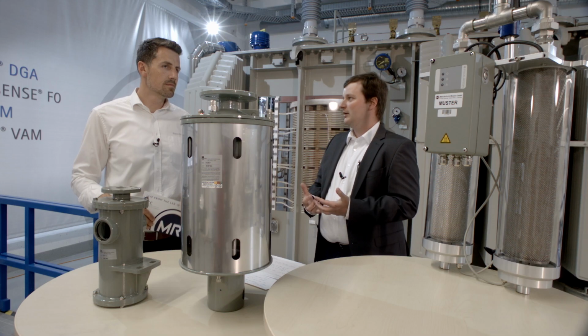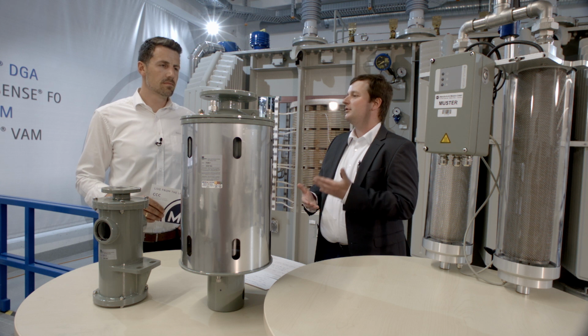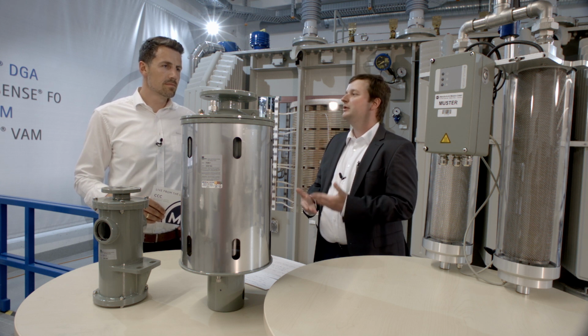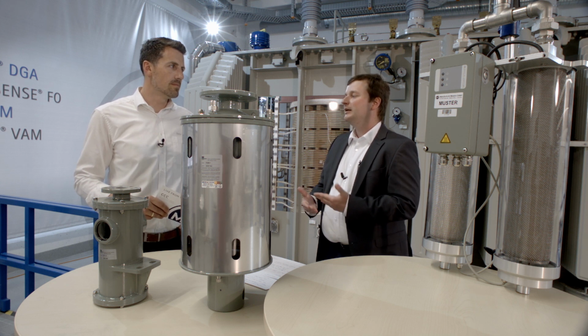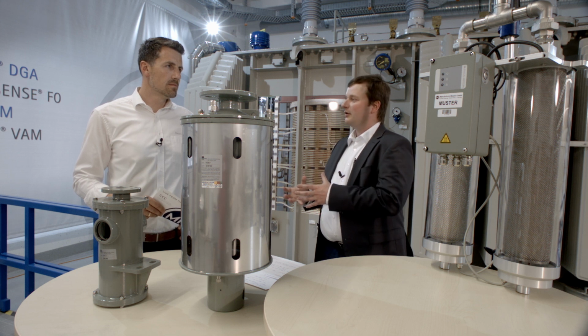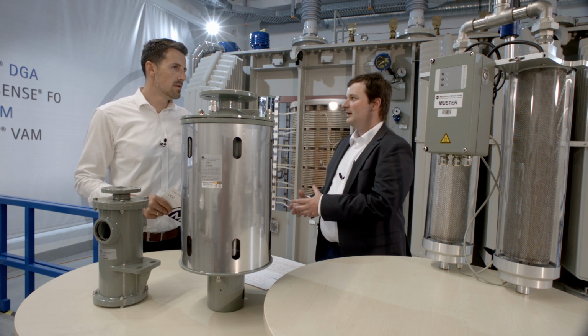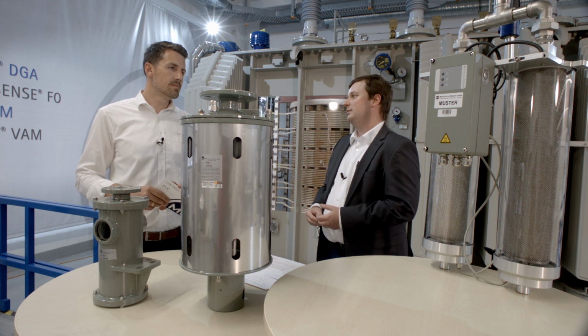There's a test button on the side, and most important for today's applications, it is future ready, with Modbus and analog outputs for humidity and temperature, showing the breathing pattern of your transformer. This is very important. It can be connected directly to your SCADA system, or maybe to ETOS.